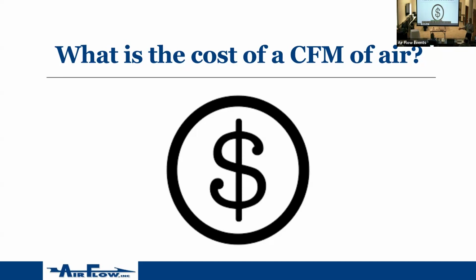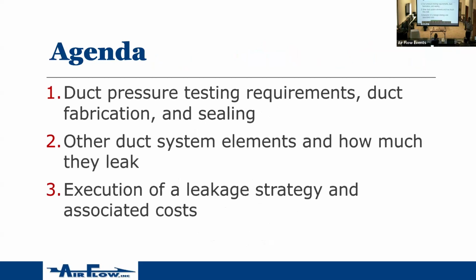So let's add filters or more filters. Let's add air conditioning, let's add heating, let's add dehumidification. What does that get up to? I've heard as high as 10, as low as 3. But if we put $5, is that a reasonable guess for how much it costs for every CFM that we blow out? Then you can get into more of the weeds, like whether it's a plenum return system or it's still in the building envelope. Maybe that's all true. But if we have some idea of what the leakage costs us, it does drive the discussion a little bit further, that maybe we ought to pay a little bit of attention to it. So I will go back and talk about, hey, is there a theoretical ROI on having better access doors? There could be, so we're gonna get there. Okay, so we're gonna talk about just ductwork for a little while.